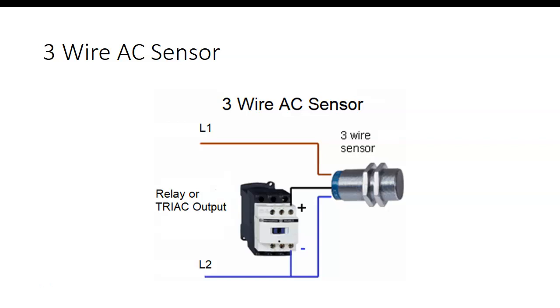Is this sinking or sourcing? I should have took that off there, that's my fault. It's sinking. Oh, so it does neither. There's that sinking or sourcing. I clipped this from the other slide, I thought I erased everything, but that's what I put my finger over, and I should put my finger over the minus. So on AC, there's no such thing. Literally, you could take the brown wire and hook it to L1, or the blue wire and hook it up to L2. You could take the blue wire and hook it up to L1, and the sensor is over here. It's just that you need to hook them up consistently, so the technician knows what to expect on these guys.